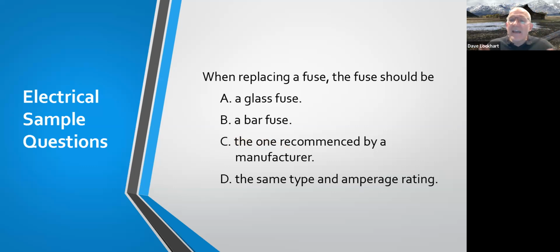Now, because of the design and what you have, it may not perfectly match the manufacturer recommendation, but you also have a challenge there that if somebody in front of you put in the wrong fuse, that's why it blew or may have problems. But the correct answer is the same type and amperage rating that you have. So I'm sure C is a very logical answer as well, and would be what you could look to, especially on a manufactured piece of equipment, enclosed equipment that was designed that way. Both could be right, but again, here they've got very close answers that either one of them probably could have been correct, but D is the correct answer. Same type and amperage rating.